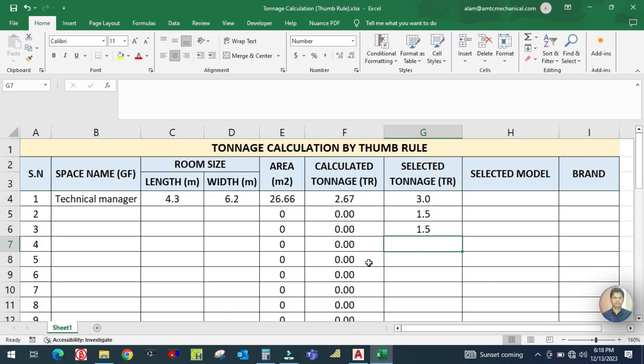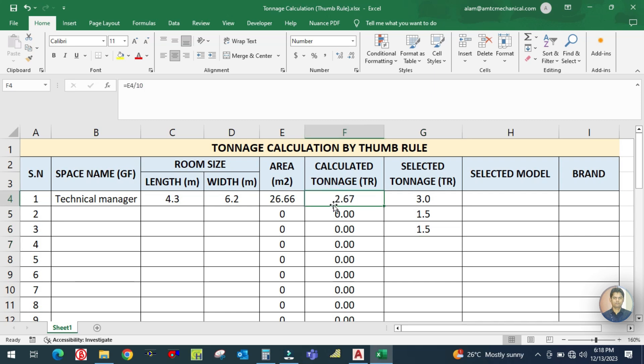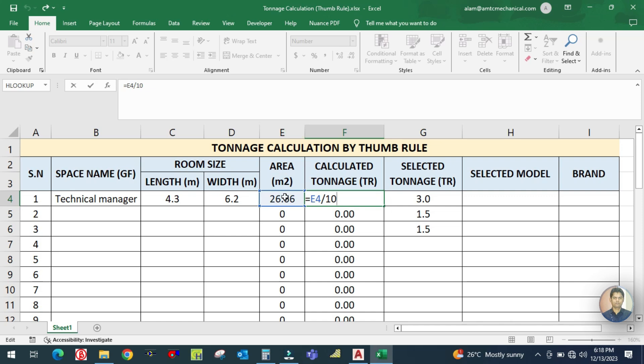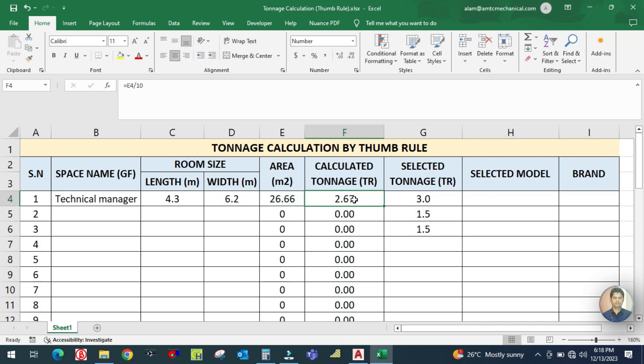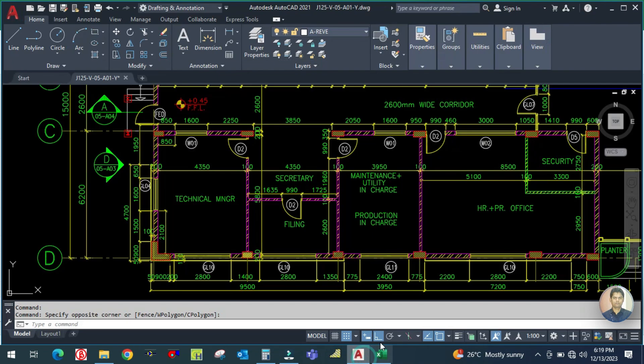There is a condition: if three walls are exposed, you use 10 square meters per ton. The calculated area is divided by 10, and I am getting 2.67 tons. Since 2.67 is not an available capacity, you always go for the next higher unit, which is 3 tons. So the selected tonnage is 3 tons. Later I will show you the model number and brand to select.